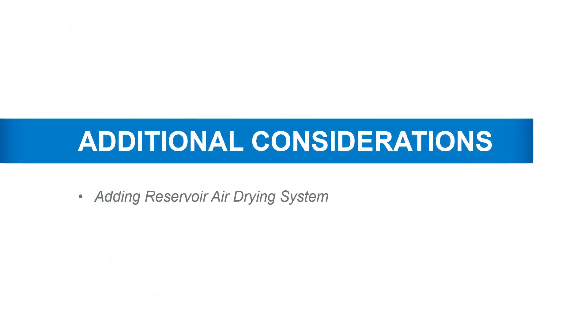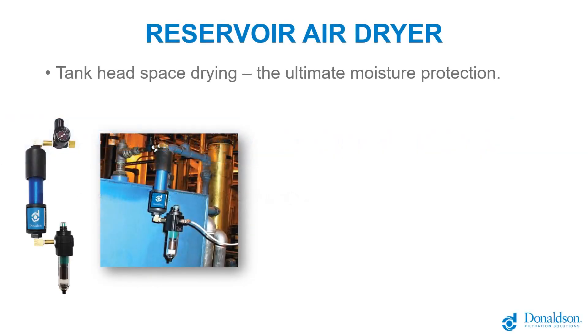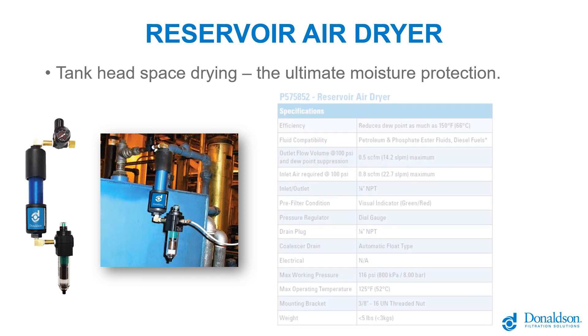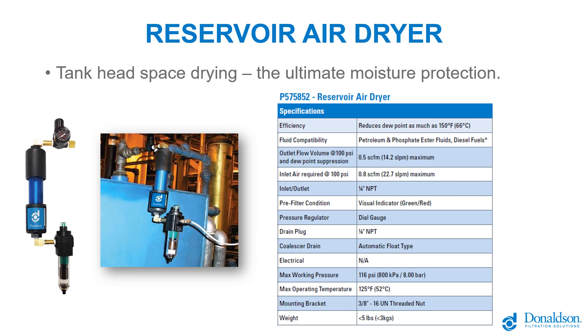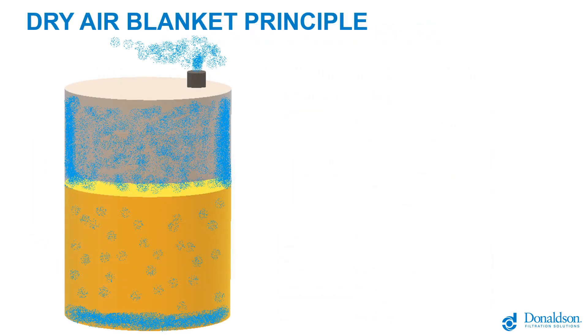Let's discuss additional considerations for keeping fluids clean and dry, including the Reservoir Air Dryer, or RAD system. Adding a RAD system purges clean dry air over the headspace of tanks to create a slight positive pressure. The RAD system requires 100 psi of shop air to operate. As the level of fluid in the bulk tank decreases and draws in air, temperature fluctuations in that headspace cause moisture to accumulate on the tank walls and run down into the fluid.